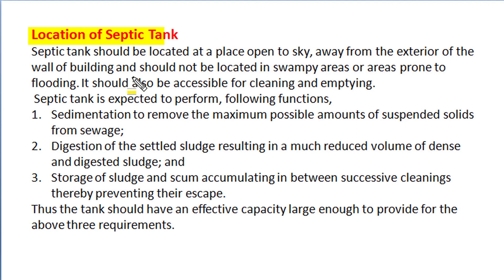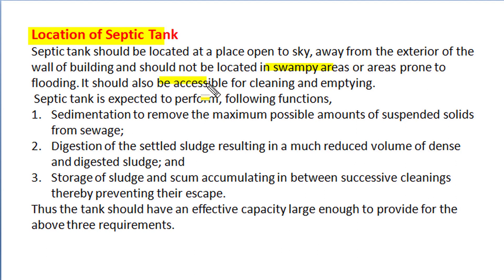The septic tank should be located at a place which is open to sky, away from the exterior wall of the building, and should not be located in a swampy area or an area prone to flooding. The location of the septic tank should also be accessible for all types of cleaning requirements or emptying by automatic pumping systems.